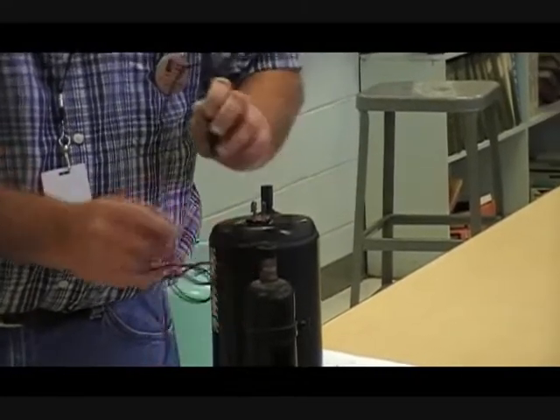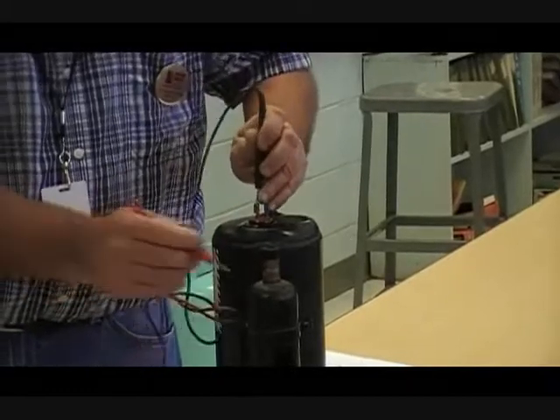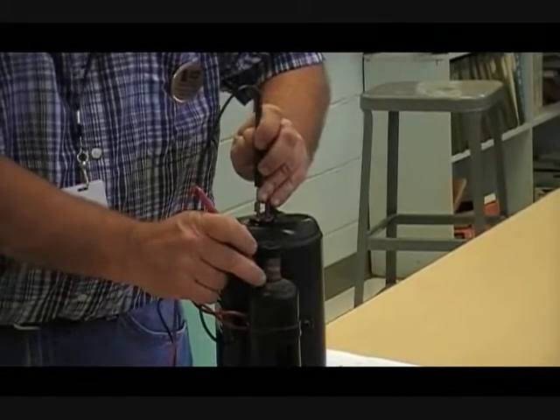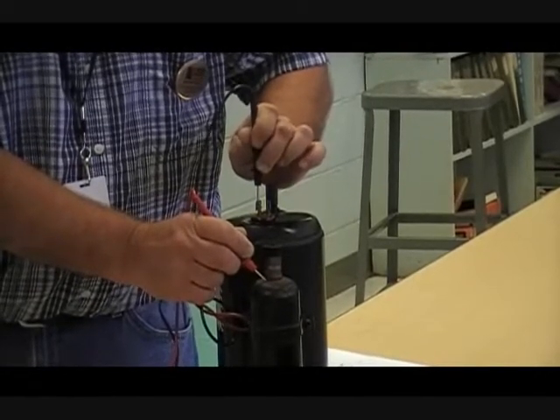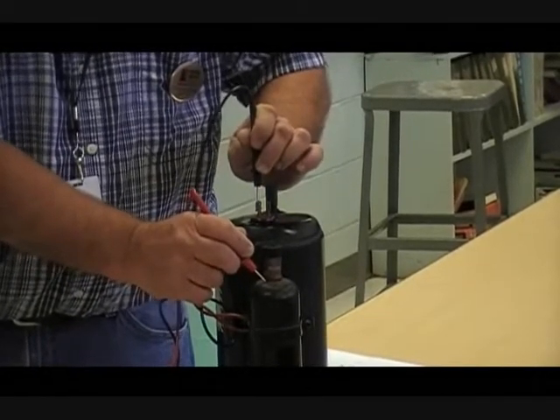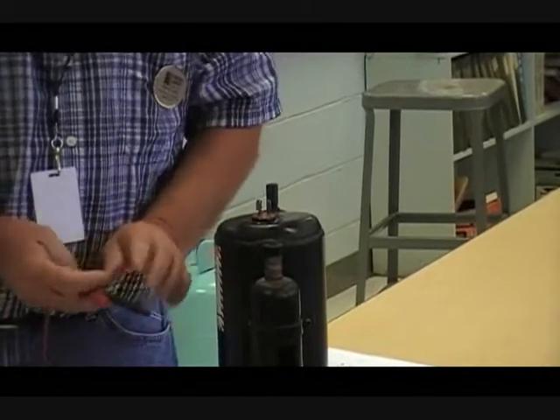One thing to be cautious of, if you're touching the leads, then it may actually show as it's being shorted. So you cannot touch the lead when you do that. This one shows that it is not shorted to ground or to the case, so the windings look good.